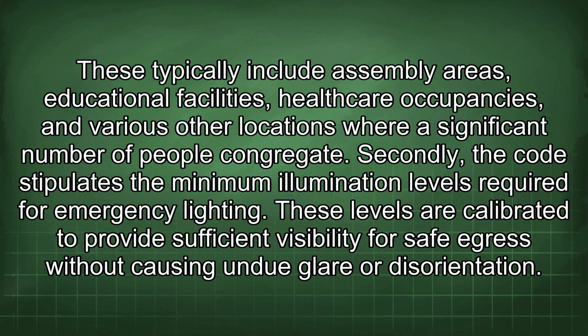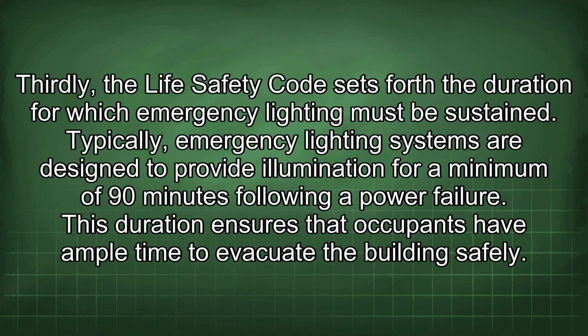Secondly, the code stipulates the minimum illumination levels required for emergency lighting. These levels are calibrated to provide sufficient visibility for safe egress without causing undue glare or disorientation. Thirdly, the Life Safety Code sets forth the duration for which emergency lighting must be sustained. Typically, emergency lighting systems are designed to provide illumination for a minimum of 90 minutes following a power failure. This duration ensures that occupants have ample time to evacuate the building safely.